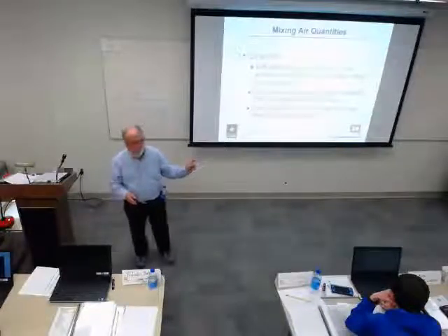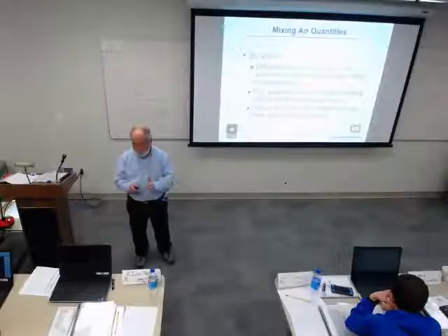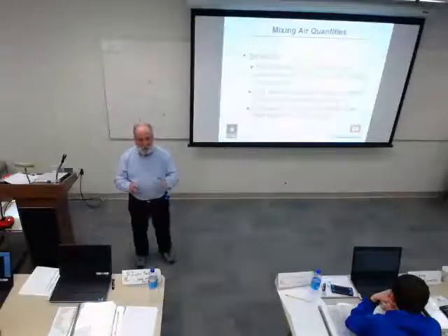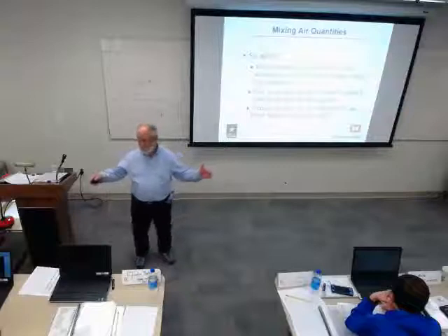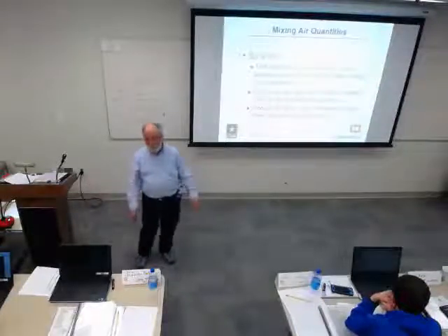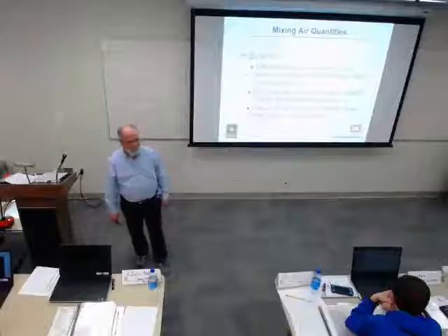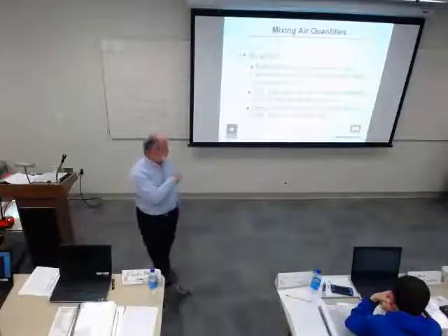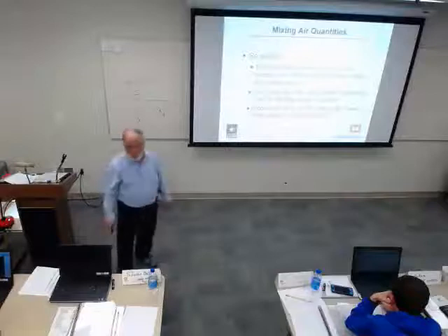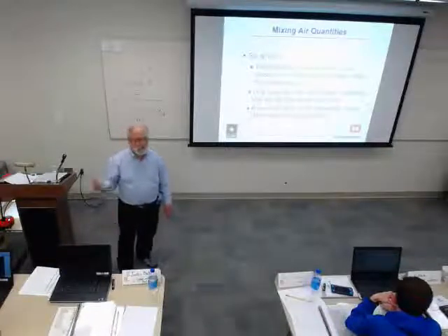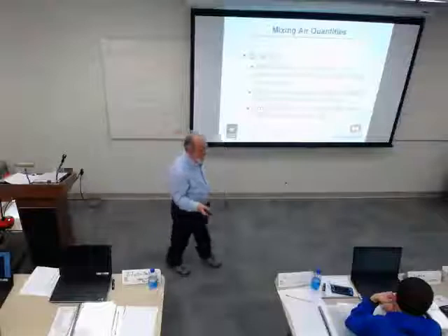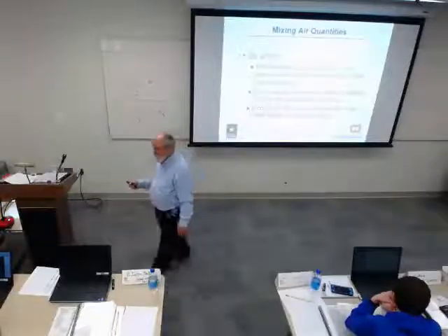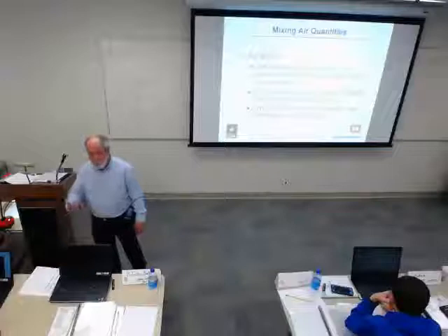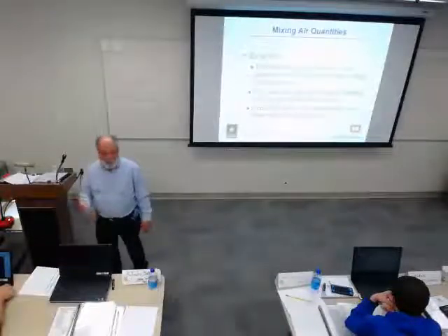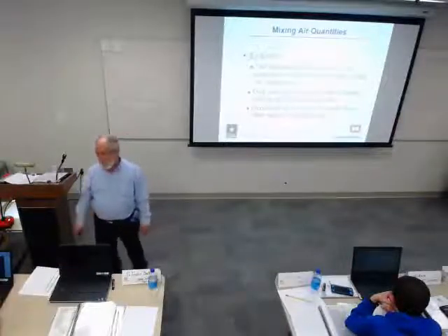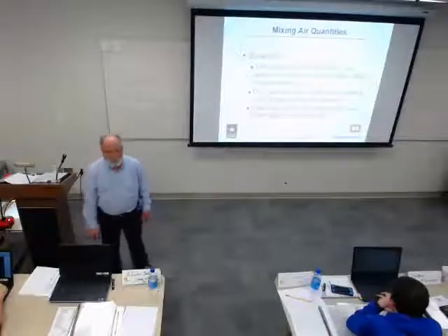So if I make a 0.5 degree error in the case where I've got a 10 degree difference, that's a pretty big deal. If I make it when I've got a 20 degree difference, it's less of a deal. And if I can get a 40 degree difference, I am happy. All right. So that's the reason why we say we only use it as a last resort, and there are times we have to. Having said that, if we know the outside air dew point and the return air dew point, we can also use dew points. Sometimes, not often, but sometimes those differences will be better, not always. So just be aware.